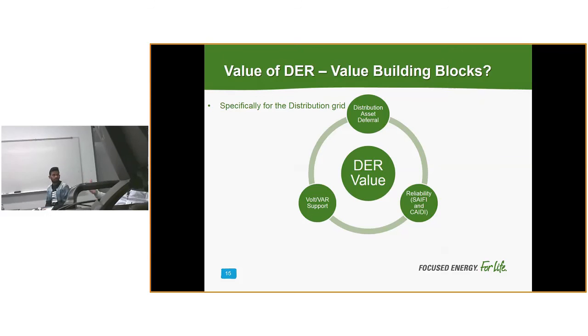To replace that transformer is a cost the rest of the customers will have to pay for. However, if DER can support during the hours the transformer is overloaded, you can defer that investment, pushing it out from 5 years to 7 or 10 years. There's value in that because you're pushing the cost into the future and not paying as much for it now. That's what we call distribution asset deferral.